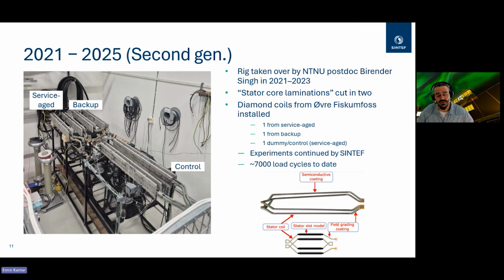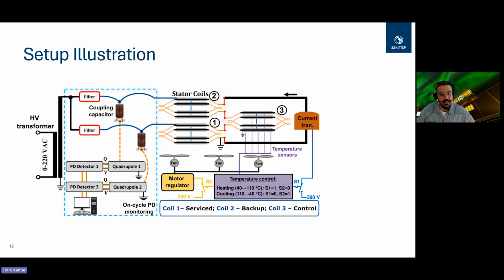Then to adapt the plant coils, we had to cut these steel plates into 2 and attach them in a way that looks as realistic as possible. In this case, we tested 1 service-aged bar, 1 backup bar, which was not used but stored in the same conditions in the plant, and 1 control or dummy coil in which we have installed some thermocouples inside. The test continued like that, and the experimental setup looks similar to the previous one. The temperature control unit controlled the heating current and the fans based on the set maximum and minimum temperatures.